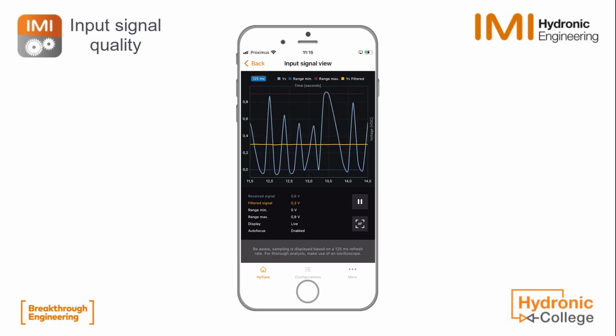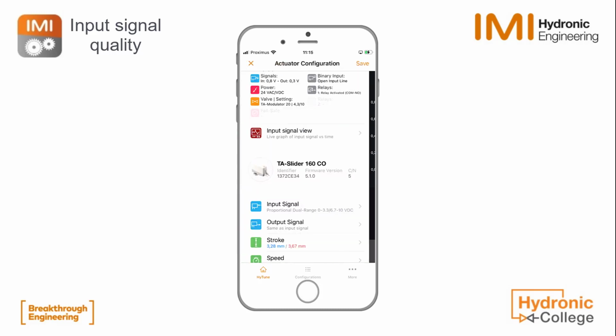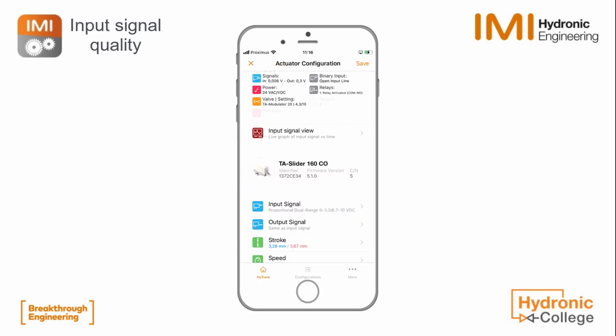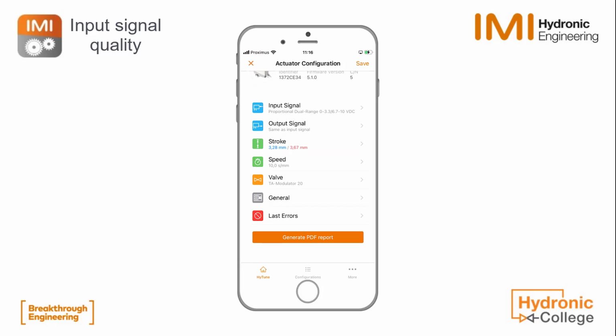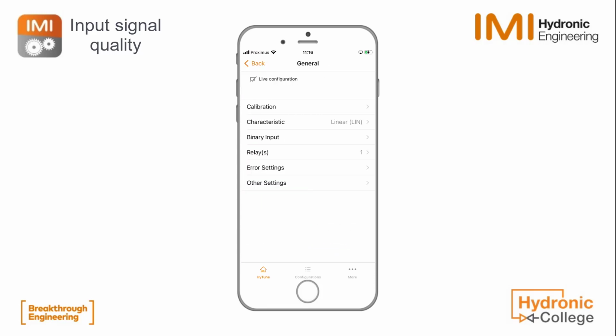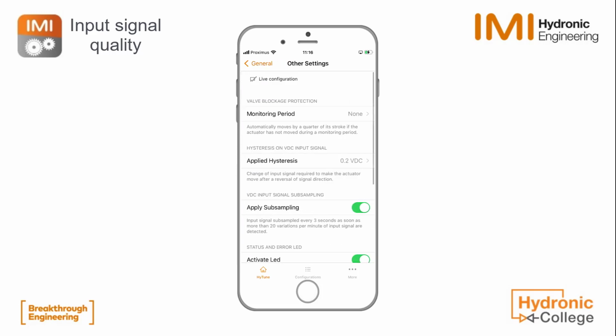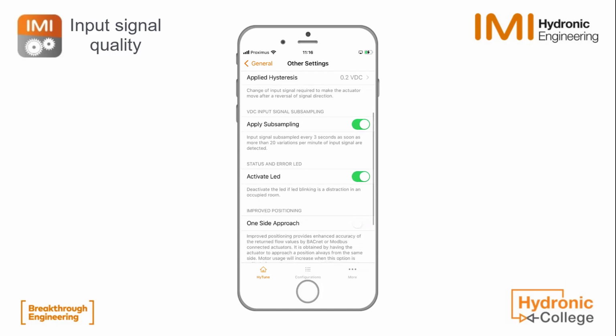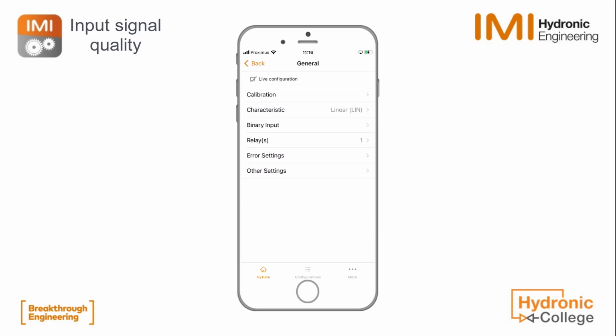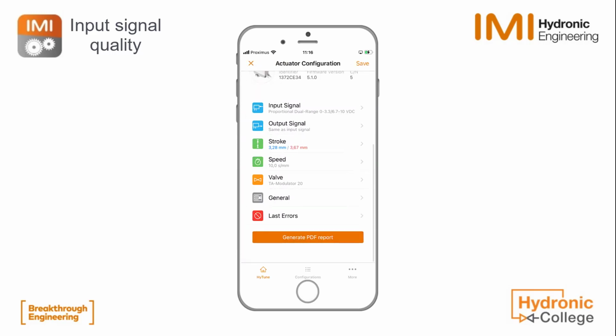Okay, so then again in other settings we can enable or disable the applied subsampling. You will see here in general we click on other settings, and then you see the apply subsampling, the VDC input signal subsampling. When we enable this, then every 3 seconds, if there is more than 20 variations per minute of the input signal, then there will be a subsampling every 3 seconds. So there are actually 2 possibilities that you can add to the already applied standard filters on the input signal.